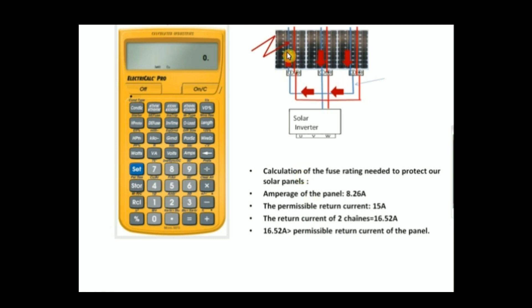And as you know, the permissible return current of the panel is 15 amps, so 16.52 amps is higher than the permissible return current of the panel. So this panel or this chain will be destroyed because we didn't provide a fuse for the protection.